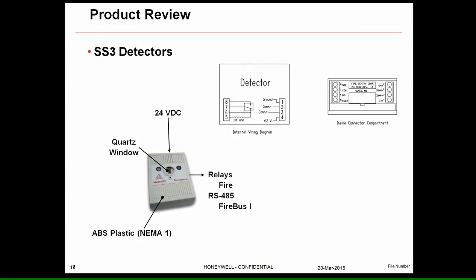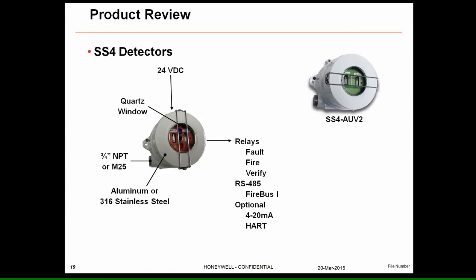The SS3 is the only non-explosion-proof detector in our portfolio. It has a small quartz window where the ultraviolet phototube is located, constructed from ABS plastic in a NEMA-1 enclosure — for indoor use only. It runs on 24V DC, has one fire relay, and allows connection to RS-485 for Firebus 1 access.